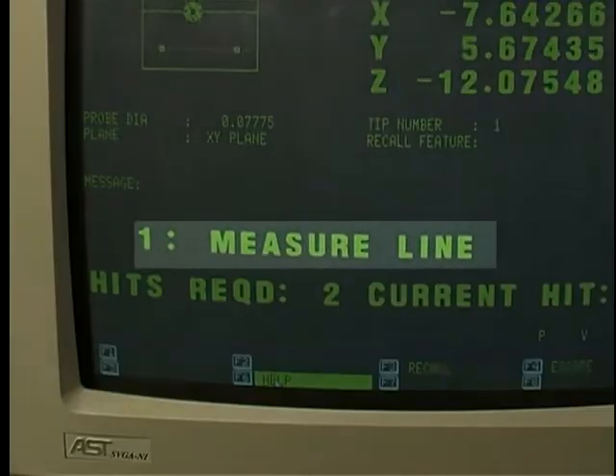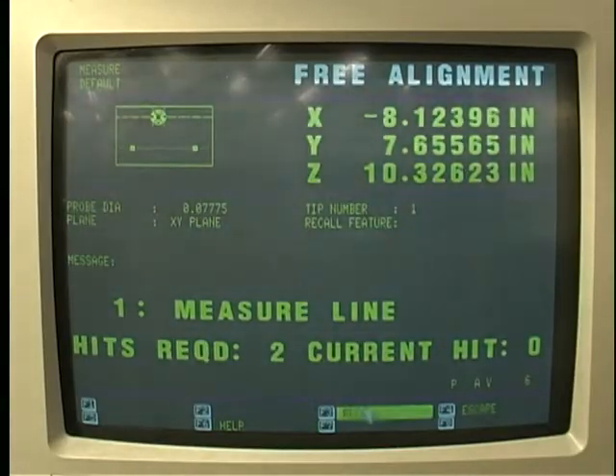The computer now asks for a major line. This requires the major axis centered at datum B. Click recall and select line 2D1. Click done.